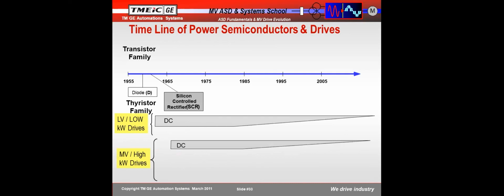Now, an SCR can turn current on. It's like a gate valve. If you pull the latch, the gate opens, and you can therefore control your current by turning it on. The problem is you can't turn it off. And so you have to have a drive topology that allows you to force the current to go in the reverse direction in order to get that turned off.